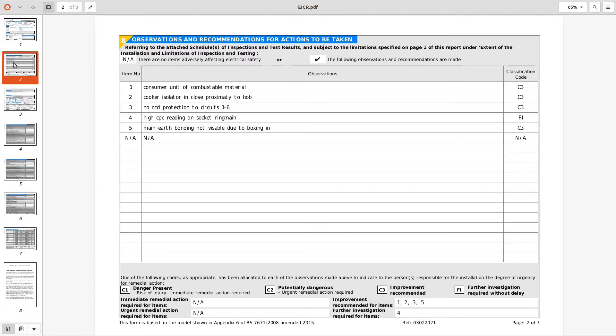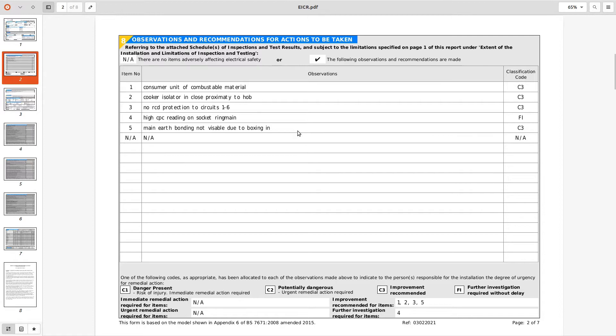Main earth bonding, main protective bonding conductors perhaps not visible due to boxing in. I think they're referring to the BS 951 clamp not being accessible the water stop tap. I would thought that they would have done an R2 wander lead test to confirm the bonding and not found the clamp. If the property is 25 year old it might be that it's plastic services anyway.